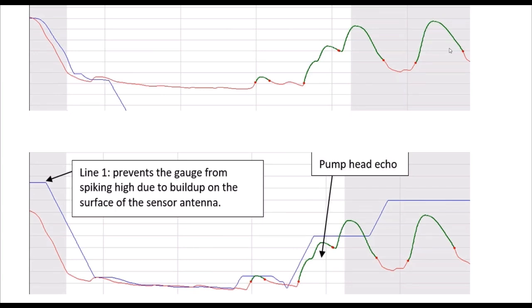Now let me explain exactly what you're looking at here, and then I'm going to explain what we're going to do. First off, mechanical floats. Got these mechanical floats down there. This particular one has just one float. Next, this reflection you see here, this is the pump head. So how this works, we're shooting a signal down in this vessel, and the red line you see here is what we call our echo curve or carrier, if you will. And then riding on this echo curve are these green humps with the 2 red dots. The green humps represent reflections returning back to the transmitter, good or bad. Now we have to learn out or map out the bad reflections so that it only tracks just the good ones.